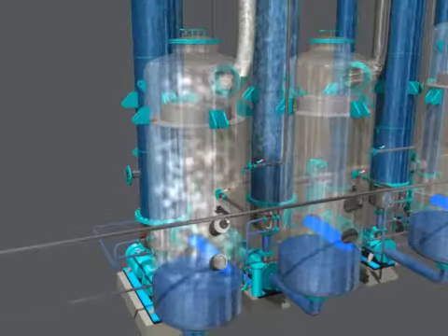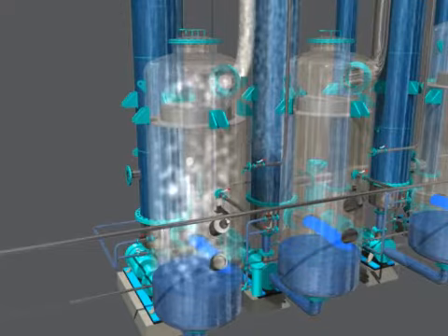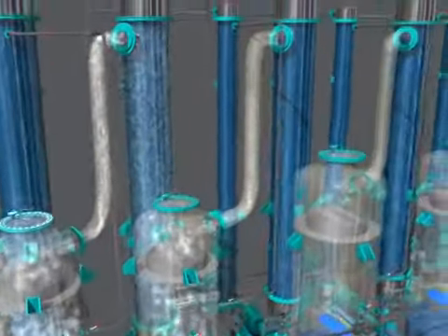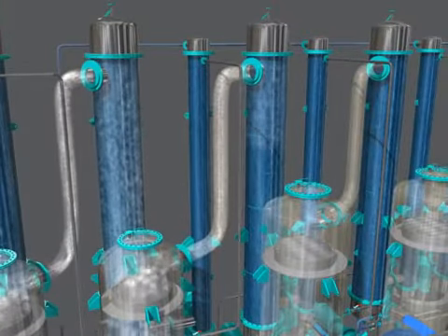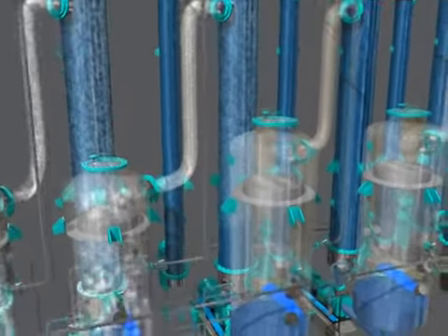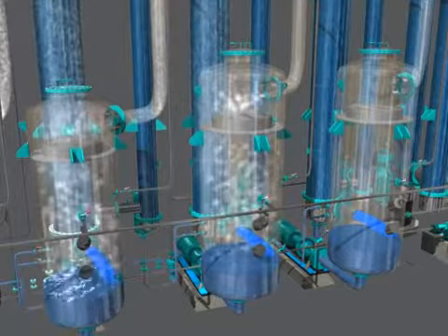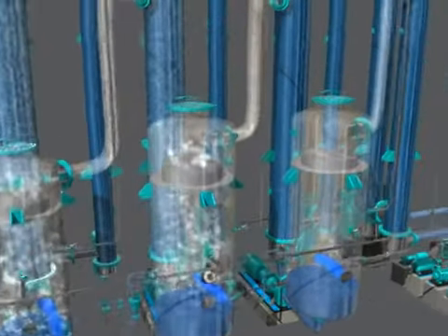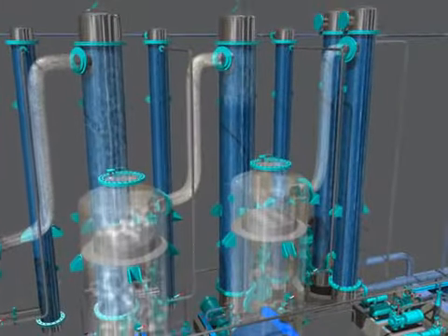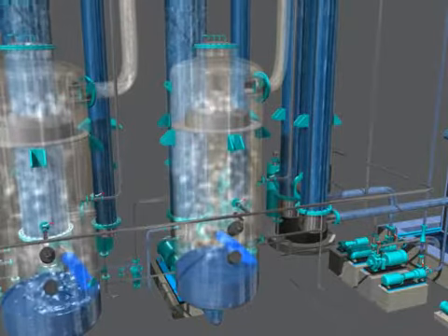In the first flash vessel, some water from the RO reject gets flashed and is converted into vapors. These vapors are carried into the next heater shell side as a heating medium by vacuum, and again the RO reject passes through the tubes, and thus there is a heat transfer between shell side vapors and tube side liquid. Subsequently, vapors are separated in a flash vessel, and the whole process is repeated in successive stages.